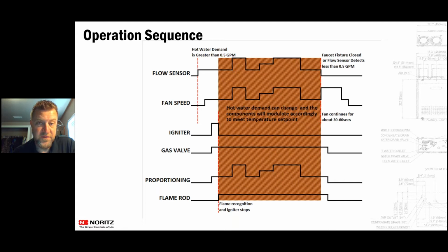What that is doing is two different things. One, it's helping keep the heat exchanger temperature from getting too high, since water's not moving through it anymore. And two, it's exiting out any unspent fuel or any flue gases that are remaining in those pipes, because with tankless condensing, you can vent in PVC and go horizontal. So we want to evacuate any flue gases, any unspent gas, anything inside of that pipe completely out of the system.